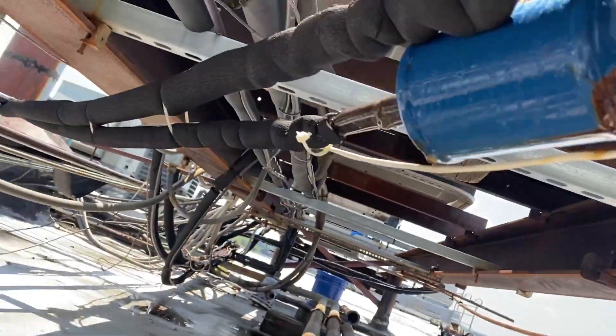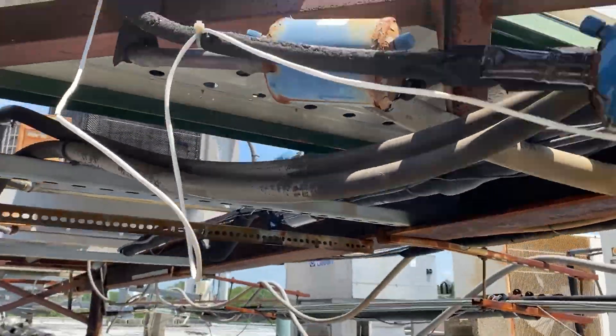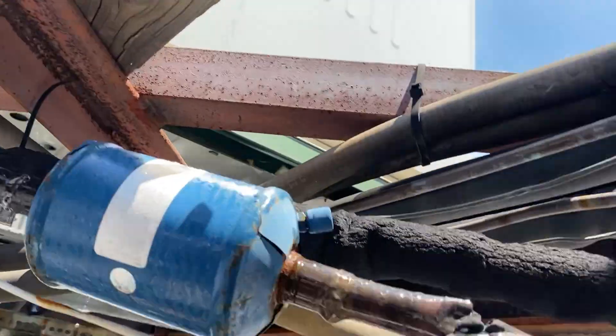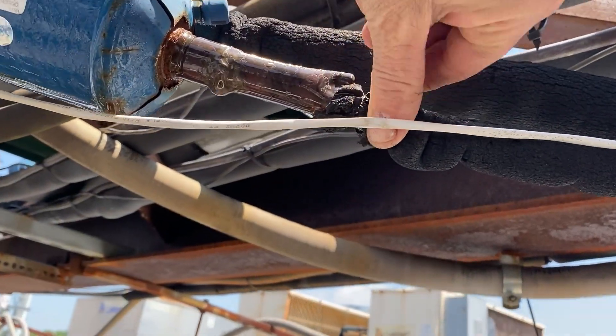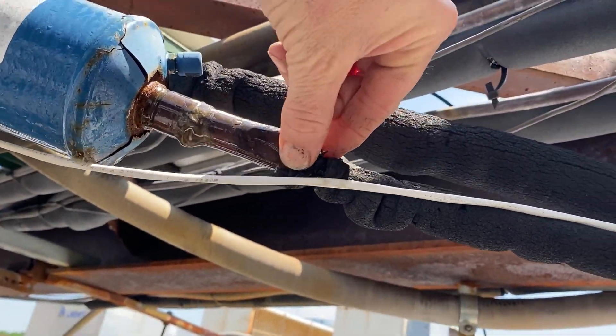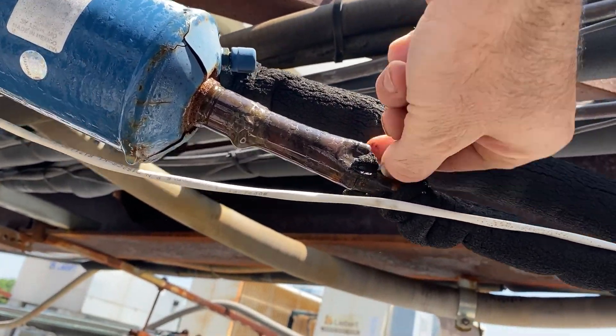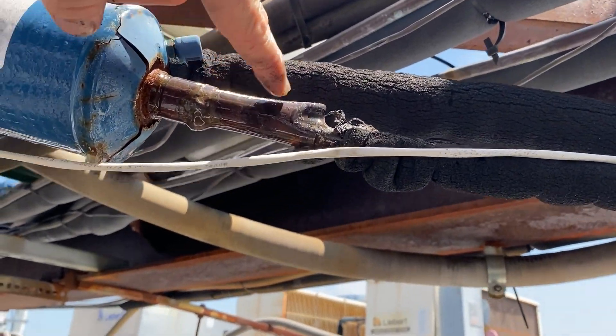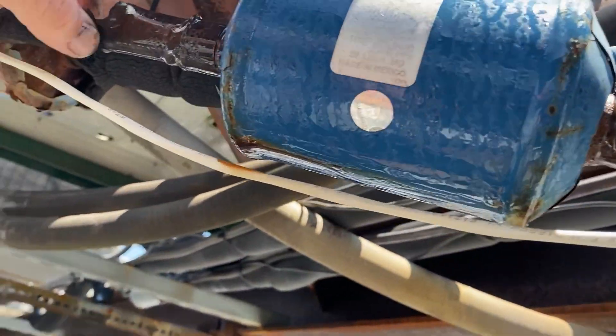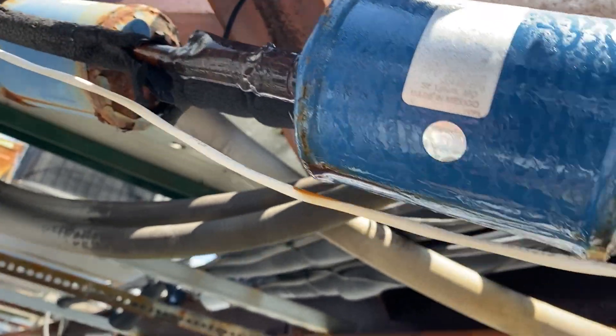It works, but then we didn't have the same thing there. Look at this — they just did not have the right dryer, so they just friggin' popped on something too big for the liquid line dryer. It's a suction line dryer and they popped it on the liquid line. Look at that, man. Both sides they had to do it on.